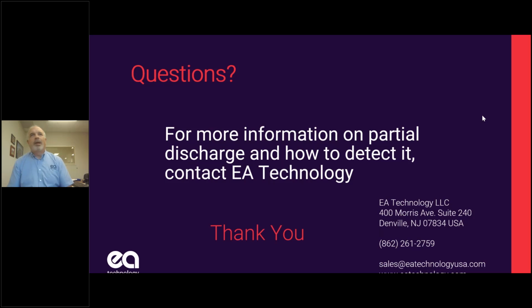Okay, well, when we talk about this electric field, the electric field is something we want to control, and anytime we have anything conductive in that field, it's going to affect it. So humidity is a little bit conductive. Salt humidity is very conductive. So if you are near a body of salt water, your cables and your terminations and anything exposed to air are going to degrade much faster.